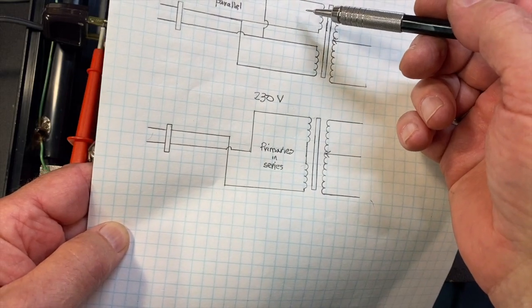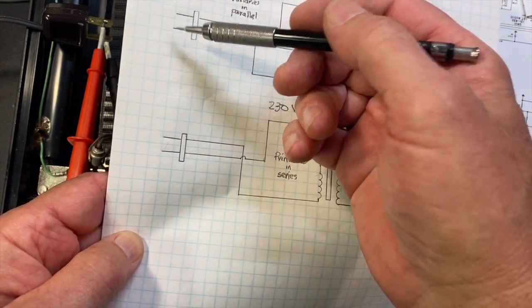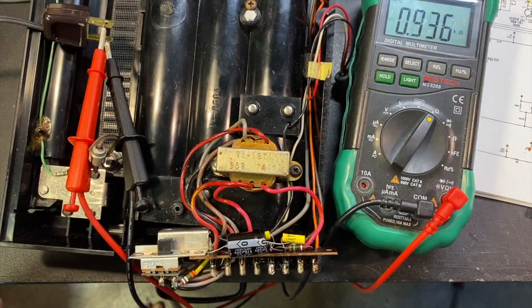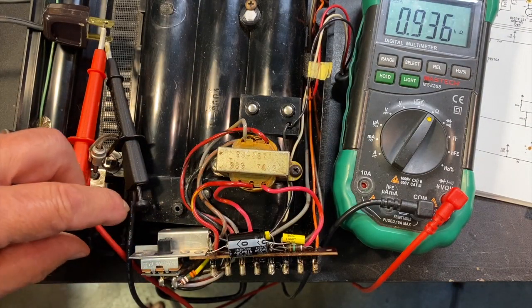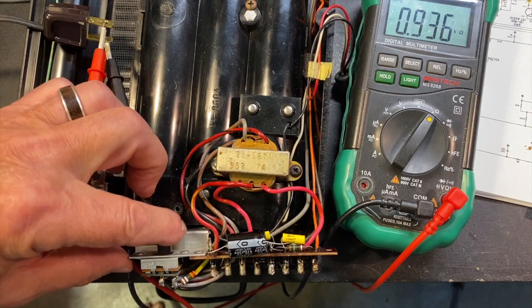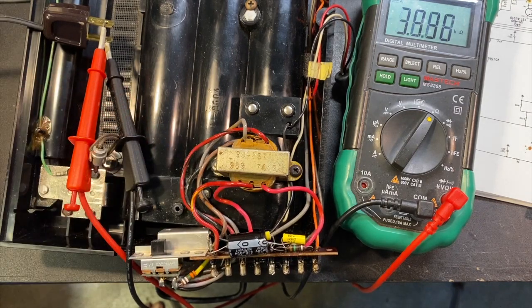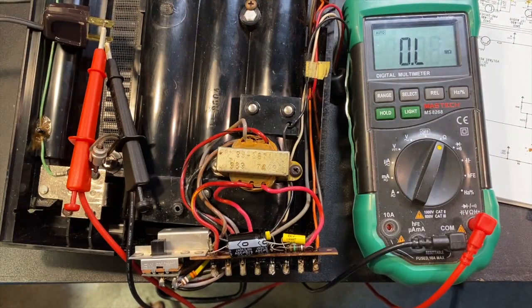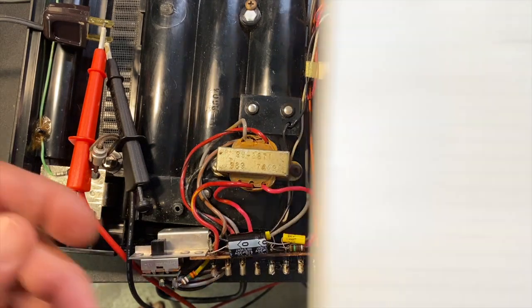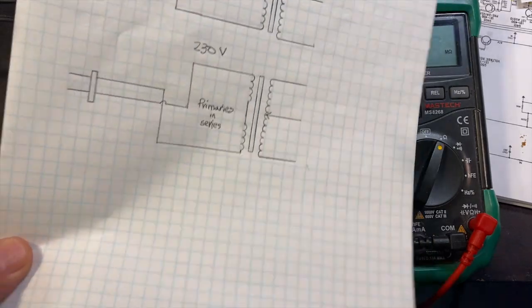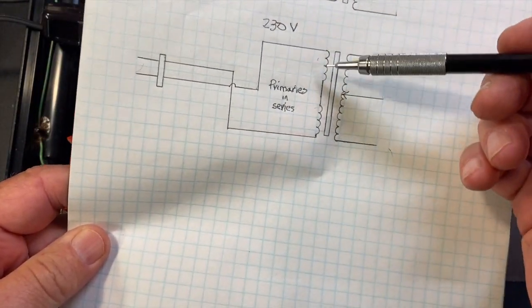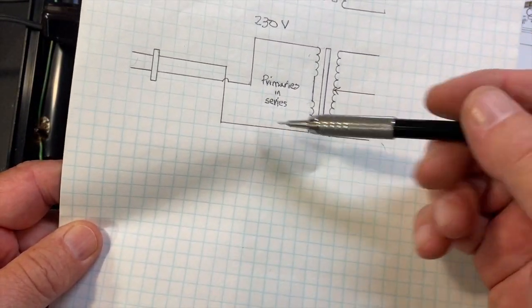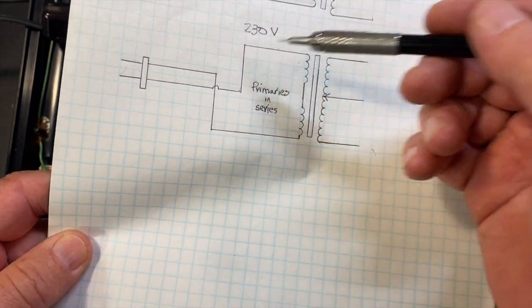I was measuring resistance across here with the meter set to the 115 volt range. If I change that to 230, which I'll do now, it says it's open, no resistance. That pretty clearly indicates that one side or the other of this transformer is open, because there's no resistance through here.